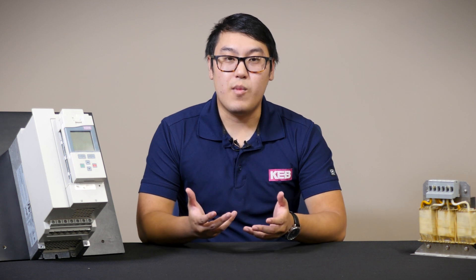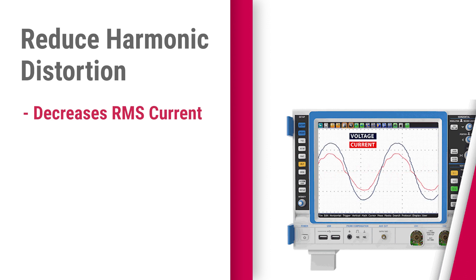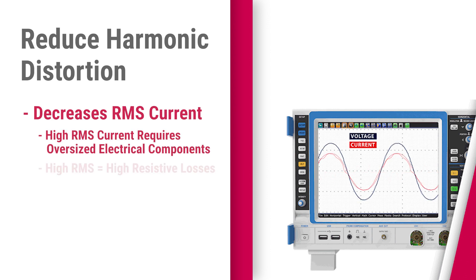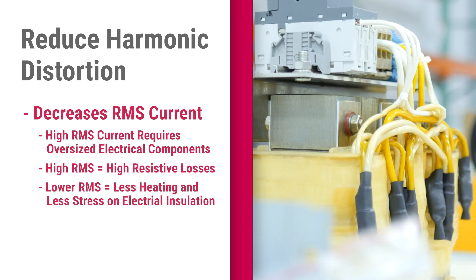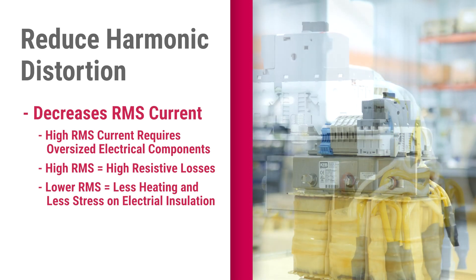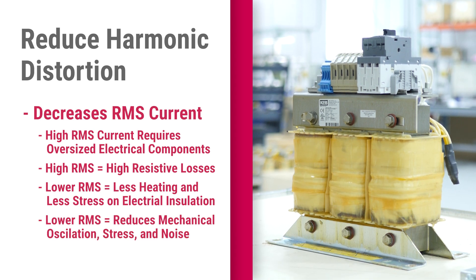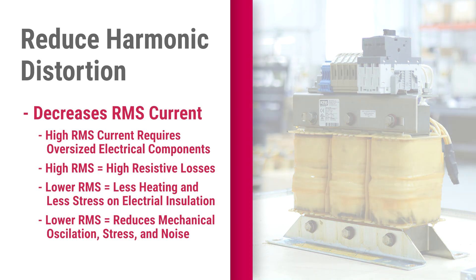Now let's talk about specifics on how our harmonic filter can reduce harmonic distortion effects. The first thing is that it decreases RMS current, which can cause oversizing of electrical components and also adds higher resistive losses. It also decreases heating on electrical components, which reduces the amount of stress put on the electrical insulation system. It also reduces mechanical oscillation in line-driven rotating components, which reduces the stress on the motor and can reduce excessive motor noise.